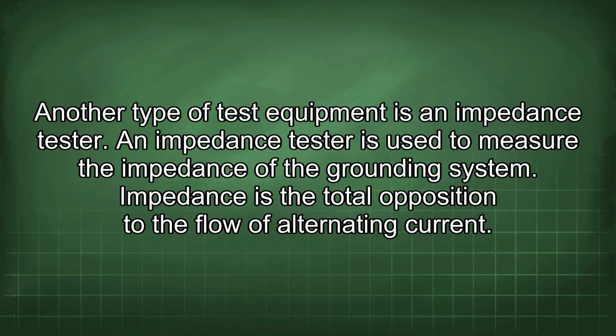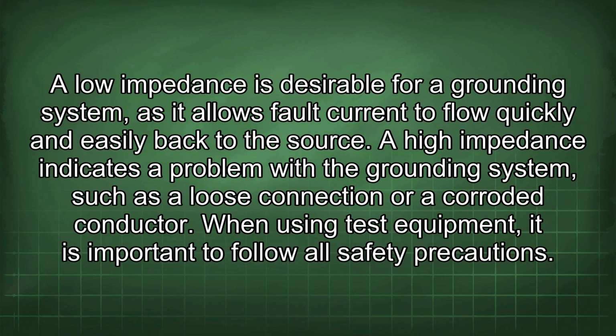Another type of test equipment is an impedance tester. An impedance tester is used to measure the impedance of the grounding system. Impedance is the total opposition to the flow of alternating current. A low impedance is desirable for a grounding system as it allows fault current to flow quickly and easily back to the source. A high impedance indicates a problem with the grounding system, such as a loose connection or a corroded conductor. When using test equipment, it is important to follow all safety precautions.